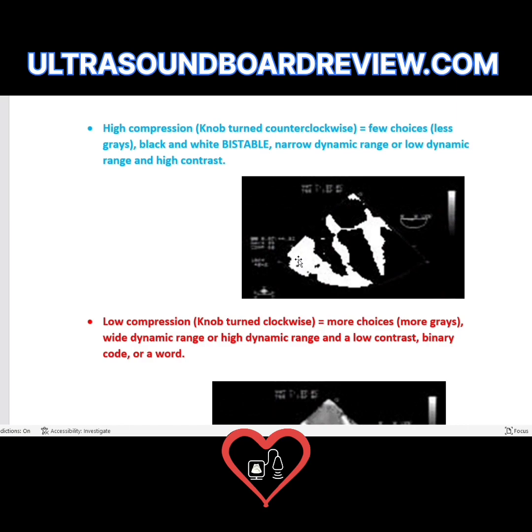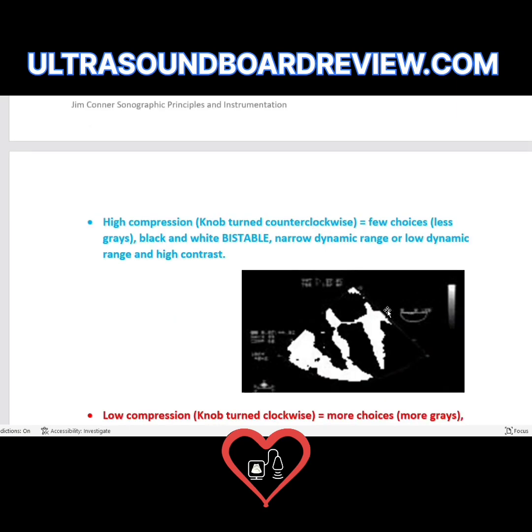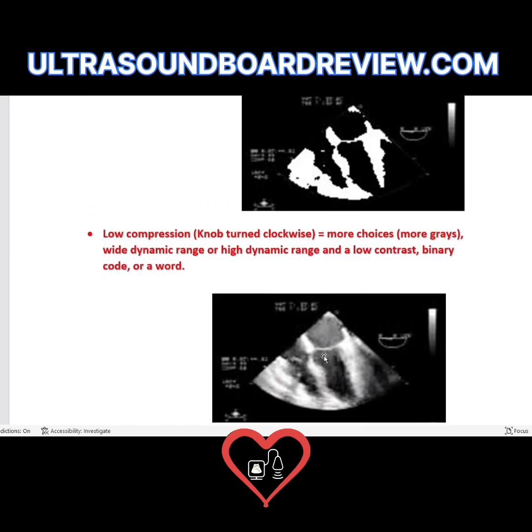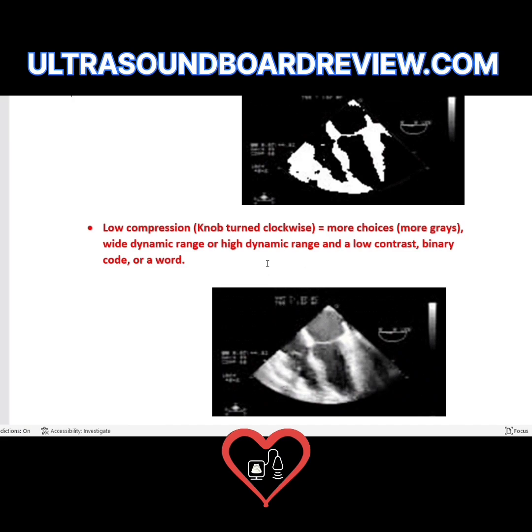The dynamic range evaluates your grayscale. The way you adjust your dynamic range is with your compression. When you turn up your compression, you're turning the knob counterclockwise, making the compression number go down — this results in fewer shades of gray and a more black-and-white image. That means you have a narrow or low dynamic range and high contrast. If you want more shades of gray, you turn the knob clockwise, which lowers your compression, making more shades of gray — this gives a wider or high dynamic range with low contrast.